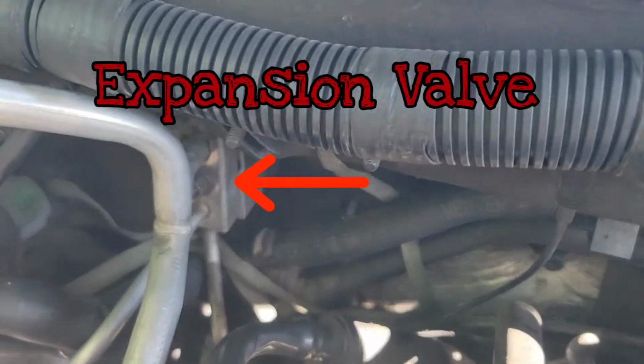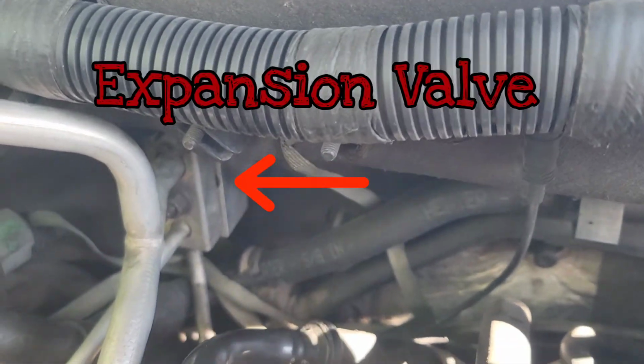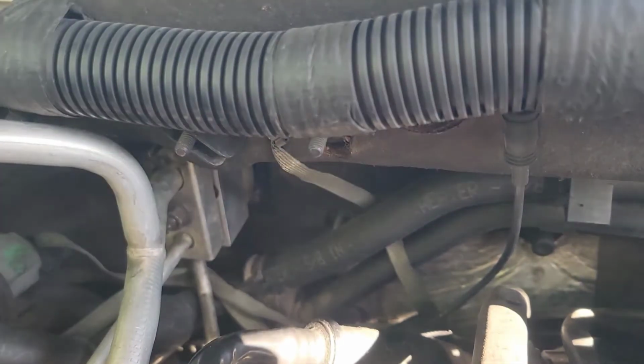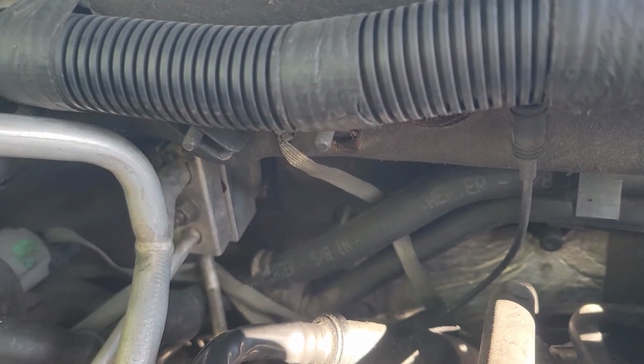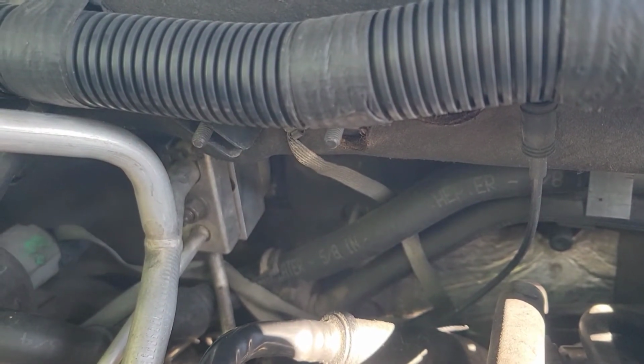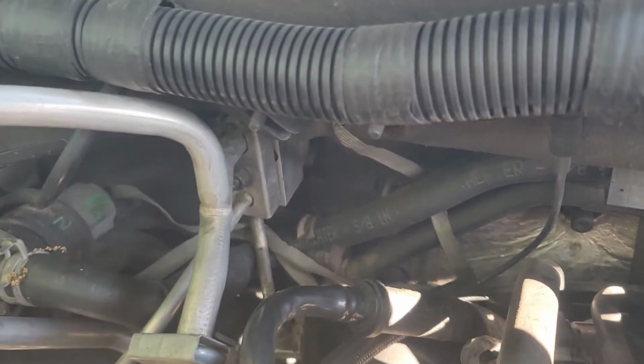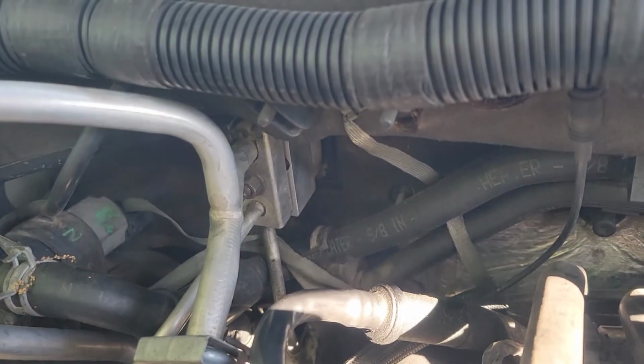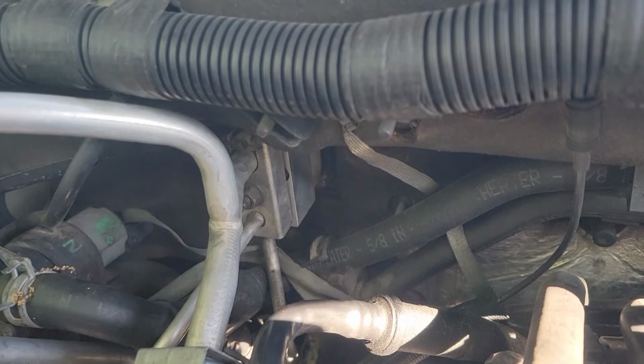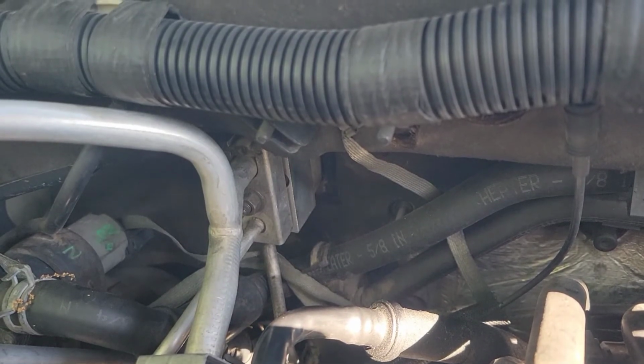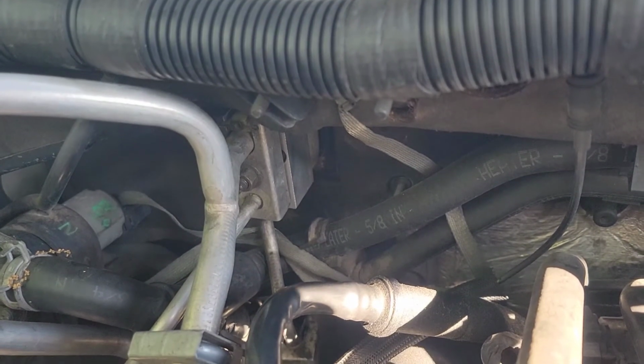The expansion valve removes high pressure from the liquid refrigerant to allow expansion or change of state from a liquid to a vapor in the evaporator. Under a greatly reduced pressure, the liquid refrigerant is at its coldest as it leaves the expansion valve and enters the evaporator.